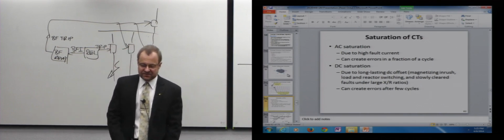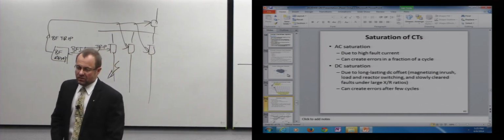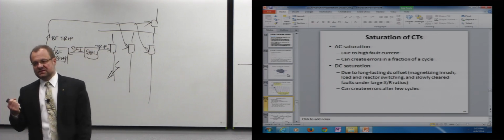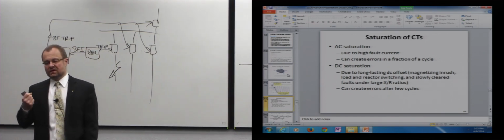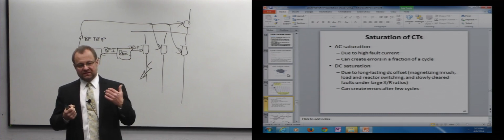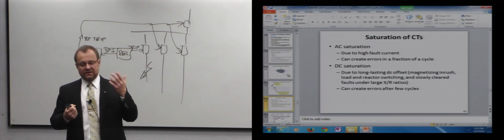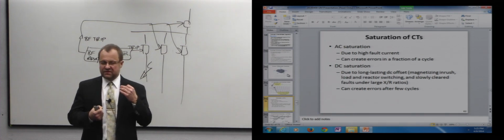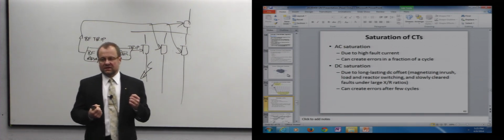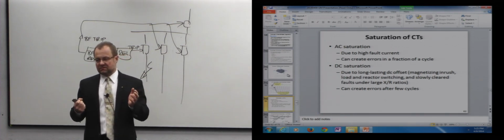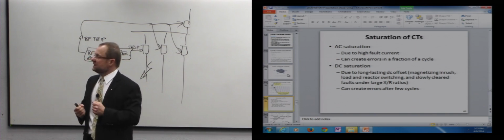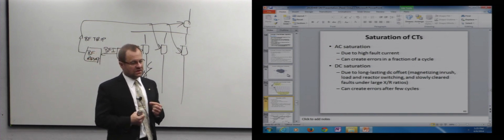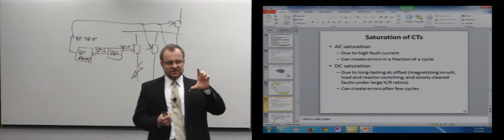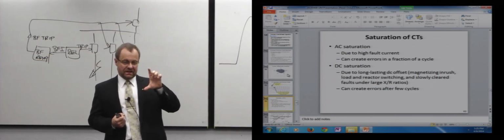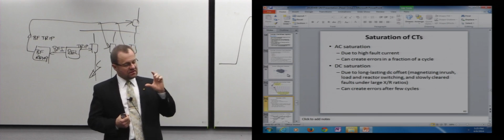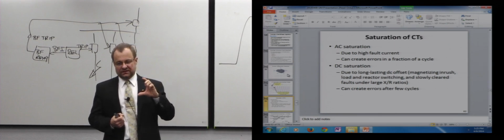There are two types of CT saturation, really. One is that you hit the CT with such a high current that you are driving the flux in it so high that it will saturate after a few milliseconds, and that's it. It will choke effectively. The other type of saturation is that you have a relatively small current, but that current has a very long-lasting DC offset in it.